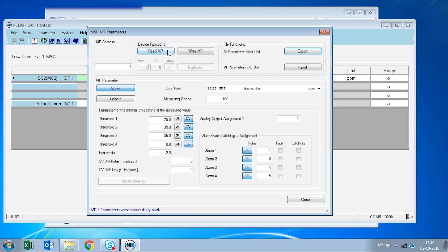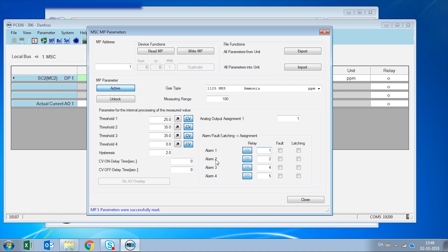The sensor is an ammonia, 100 ppm range and we can see that it has two alarm levels, one at 25 ppm and another at 35 ppm. The way that these alarms react is alarm 1 activates relay 1 and alarm 2 activates relay 2. We can also assign those relays and alarms to be activated when there is a fault or have the alarm latching which means that it will stay on regardless if the gas is gone until someone acknowledged the alarm.